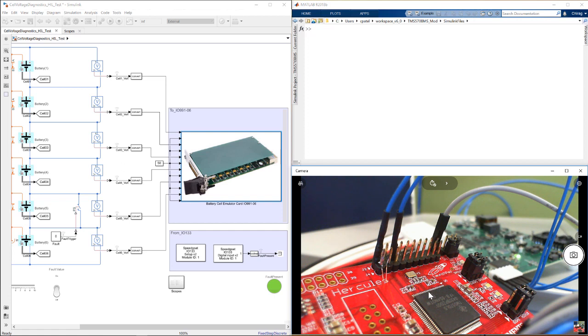The BMS controller performs diagnostics on cell voltages and generates a fault status in the case of an over or under voltage fault or a short between two terminals. In this case, the BMS controller turns on the LED in the event of a fault and outputs its status on a digital output port. We read the fault status from the BMS controller using the digital input port of IO133 to check if the controller logic is performing as per the requirement. Now let's go ahead and connect to the target machine.